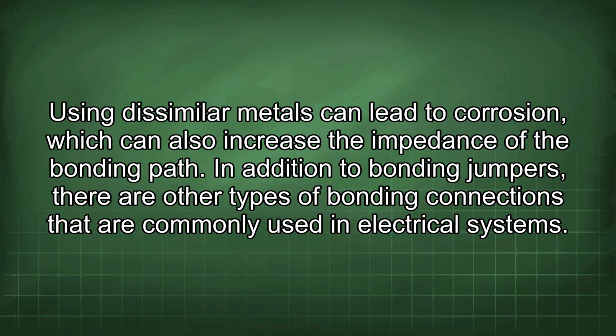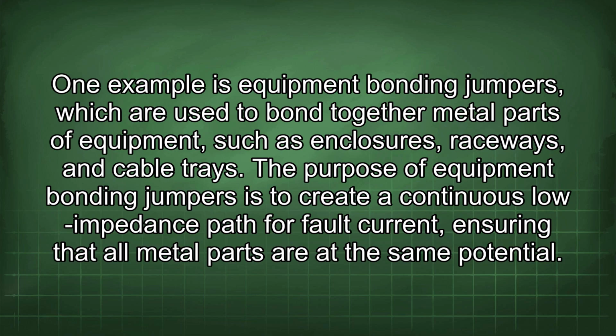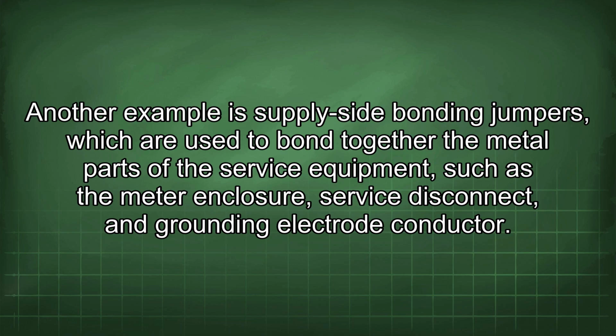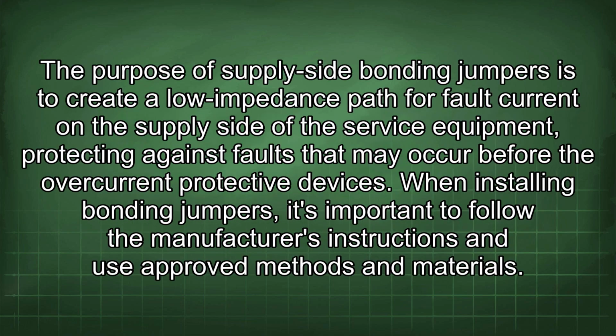In addition to bonding jumpers, there are other types of bonding connections that are commonly used in electrical systems. One example is equipment bonding jumpers, which are used to bond together metal parts of equipment, such as enclosures, raceways, and cable trays. The purpose of equipment bonding jumpers is to create a continuous low impedance path for fault current, ensuring that all metal parts are at the same potential. Another example is supply-side bonding jumpers, which are used to bond together the metal parts of the service equipment, such as the meter enclosure, service disconnect, and grounding electrode conductor. The purpose of supply-side bonding jumpers is to create a low impedance path for fault current in the supply side of the service equipment, protecting against faults that may occur before the overcurrent protective devices.